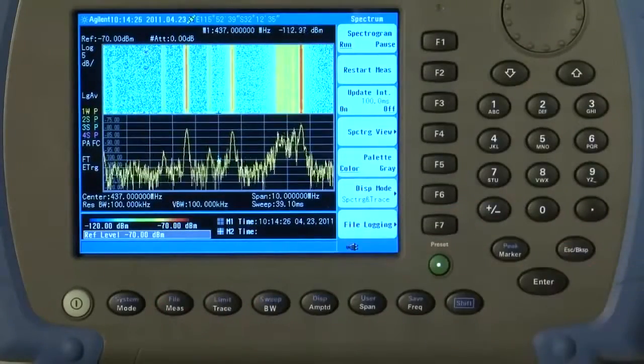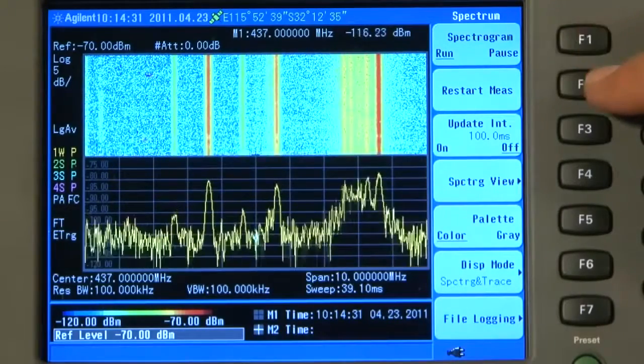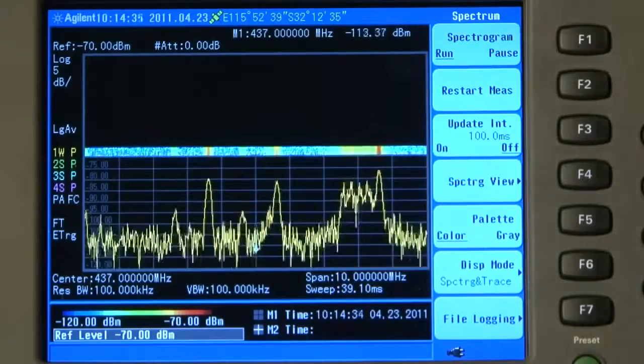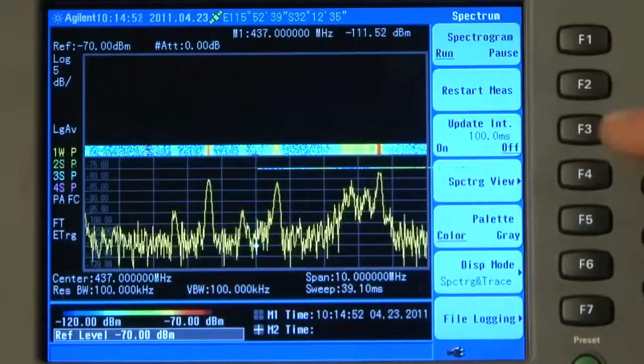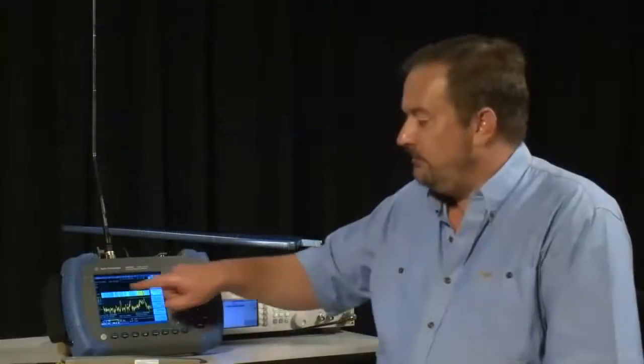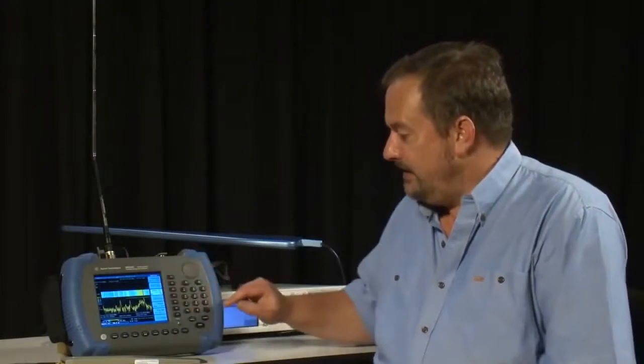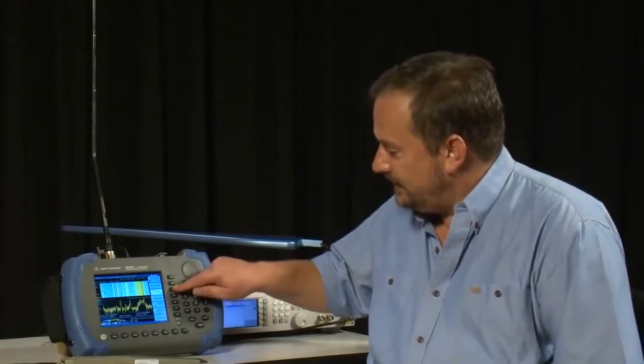If I press the Measure button, you will see here we can pause and run the spectrogram. We can restart the measurement, clearing all the traces that we have stored in the internal memory. And we can even set the Update Interval, currently set to 100 milliseconds. But let us say I wanted only to record a new trace every 10 seconds, for example. I could type in 10 seconds for that. And now the instrument will pause for 10 seconds and then add a new measurement to that stack of traces in the spectrogram display. I will set the Update Interval back to its fastest, 100 milliseconds.